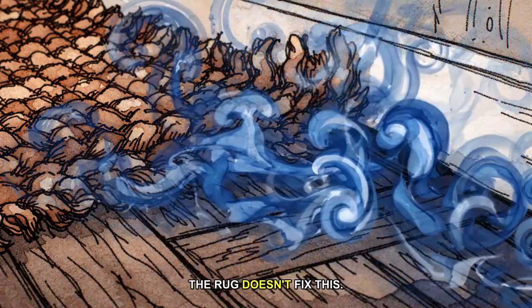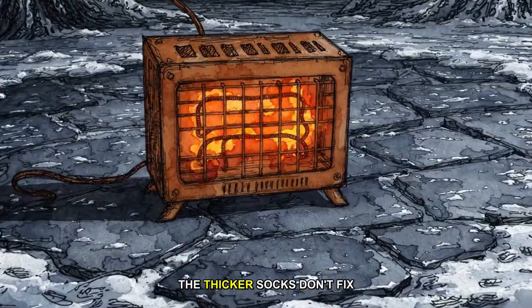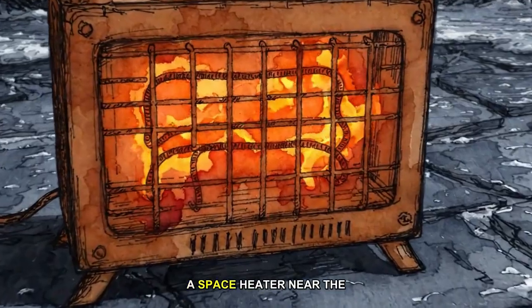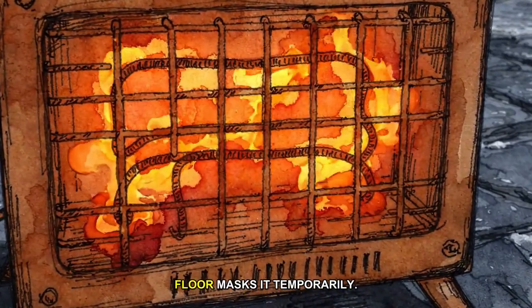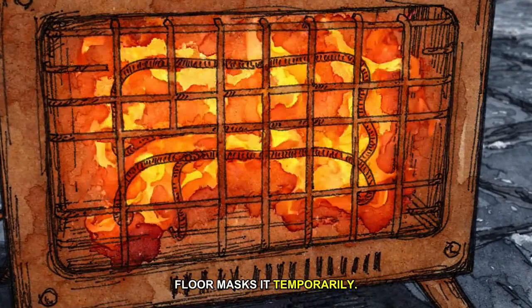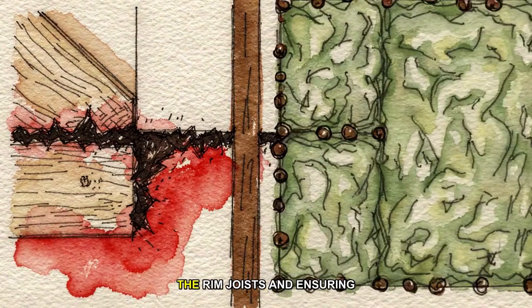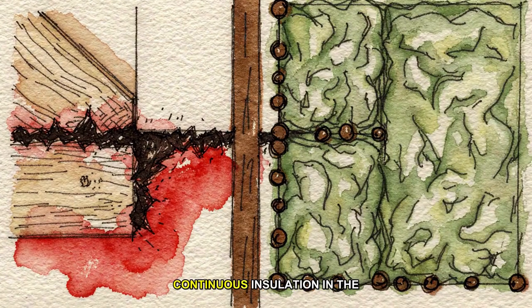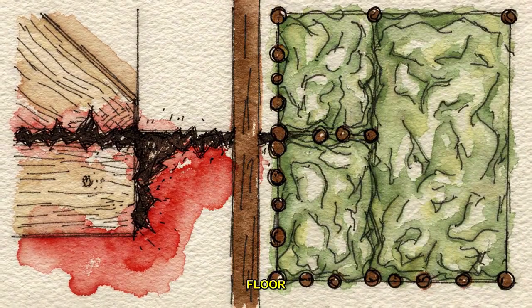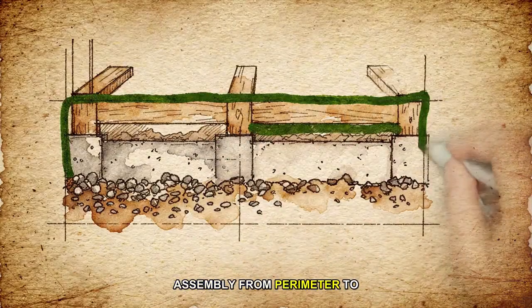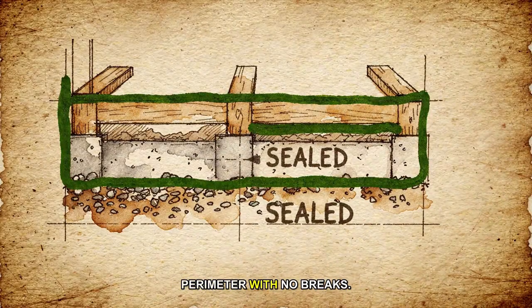The rug doesn't fix this. The thicker socks don't fix this. A space heater near the floor masks it temporarily. The fix is air sealing the rim joists and ensuring continuous insulation in the floor assembly from perimeter to perimeter, with no breaks.